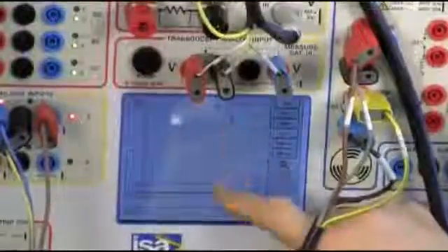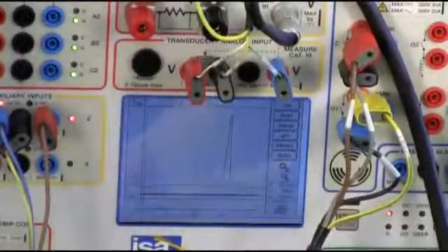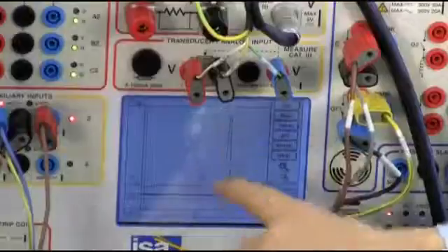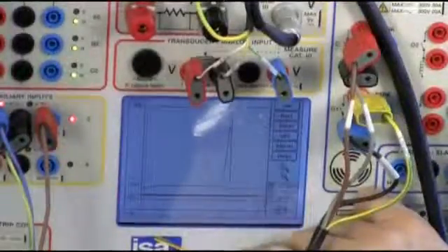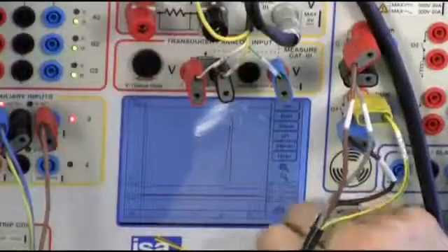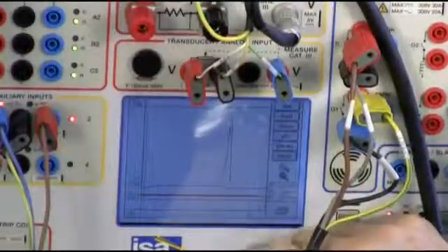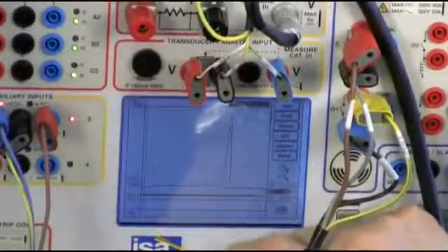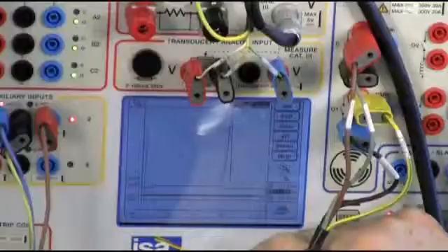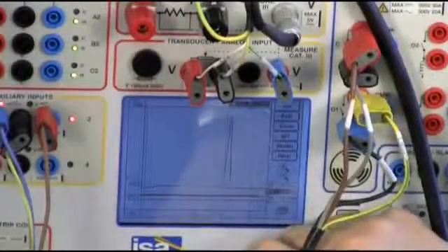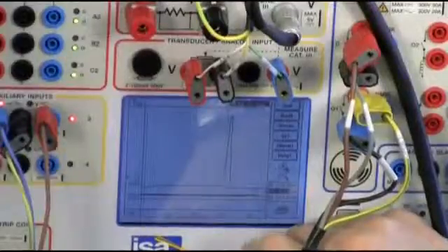Here it is. The interesting part is this one, and as you can see, it is a linear resistance change from these few micro ohm actually. Okay, 600 micro ohm, up and up and up, until the contact was completely open.